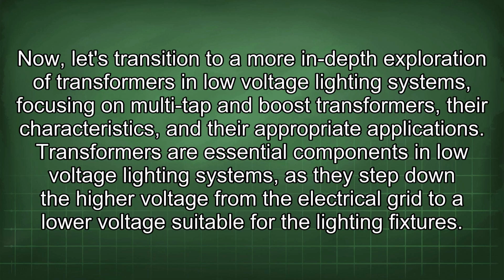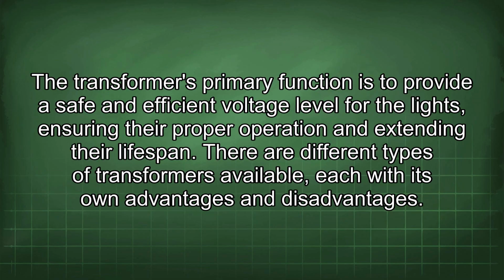Now, let's transition to a more in-depth exploration of transformers in low-voltage lighting systems, focusing on multi-tap and boost transformers, their characteristics, and their appropriate applications. Transformers are essential components in low-voltage lighting systems as they step down the high voltage from the electrical grid to a lower voltage suitable for the lighting fixtures. The transformer's primary function is to provide a safe and efficient voltage level for the lights, ensuring their proper operation and extending their lifespan. There are different types of transformers available, each with its own advantages and disadvantages.